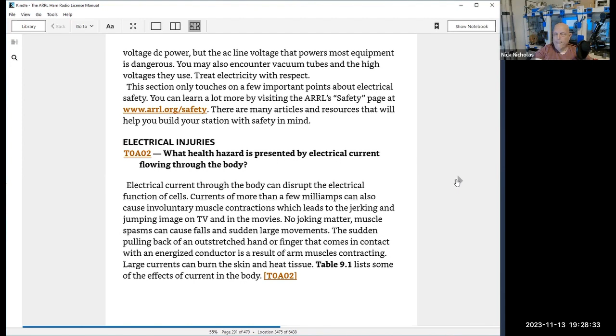Another rule of thumb I want you to remember. As a rule, I'll give you an honest statement here, and I'll go through this chart in a second. As a rule, electricity can jump through the air, or arc. You should use a rule of about 1 inch per 1,000 volts. Now let's see what that means. Well, 440 voltage, about 500 volts, can jump about 1/2 inch. So a 1/4 inch to a 1/2 inch, depends upon the humidity and other characteristics at the time and where you're at.